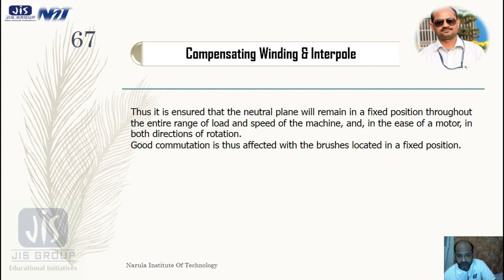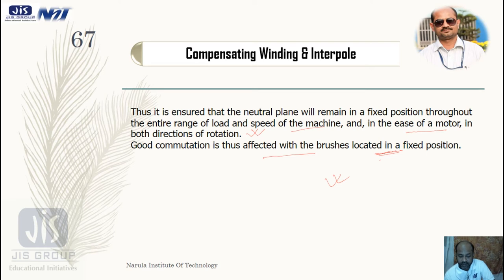This is how it ensures the neutral plane remains fixed, and in case of a motor, in both directions of rotation. Good commutation is thus effected with the brushes located in a fixed position. This is the concept of compensating winding: this winding is placed in the main pole faces and connected in series so that the same armature current flows through it, so that the compensating winding produces the exact opposite effect to the armature MMF — because the current flowing through it is in the reverse direction compared to the adjacent armature conductor.